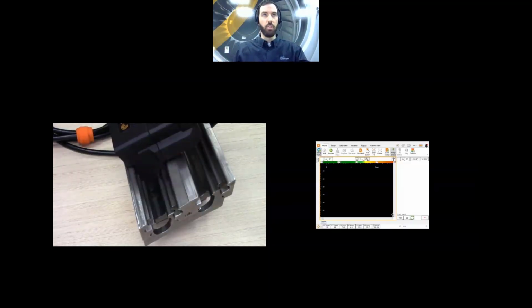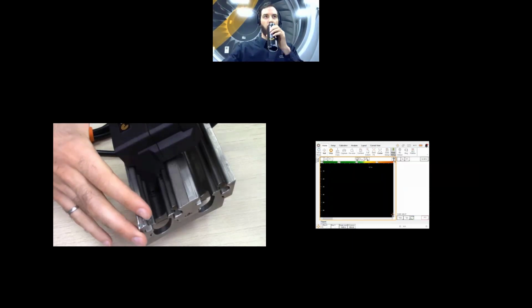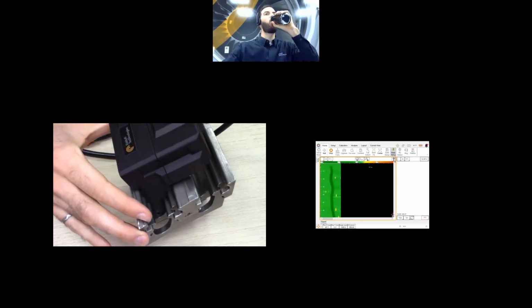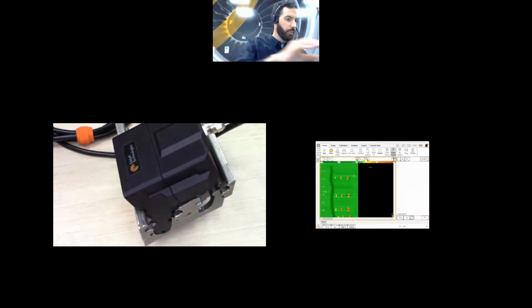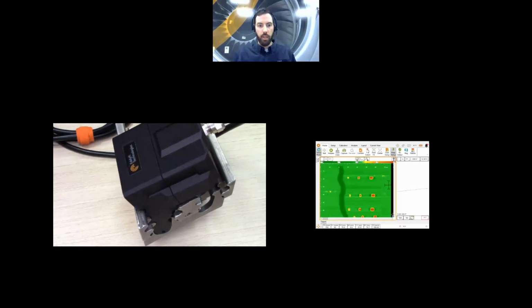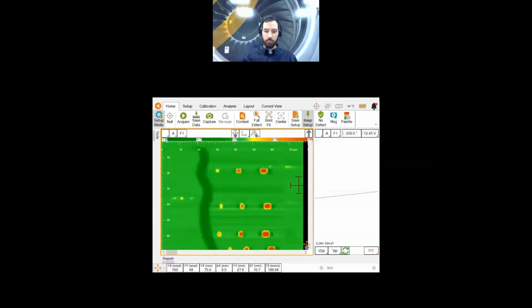So we will first null on the clean surface at the beginning, press start, and slide the probe into the slot. We can now stop the acquisition, have a closer look. And here, once again, we're not using any type of median filter, any type of custom process. This is really just the raw data coming out of that probe and displayed into a C-scan image.